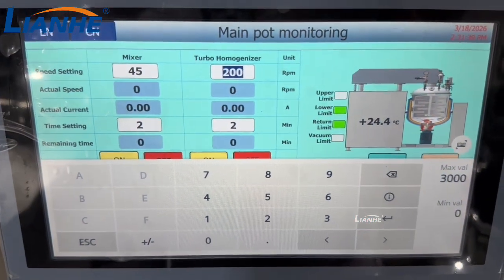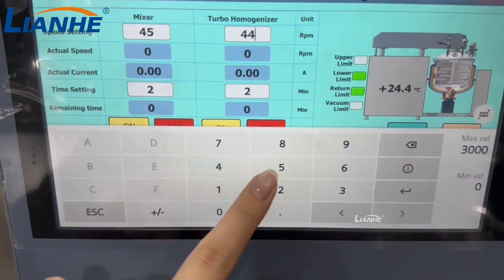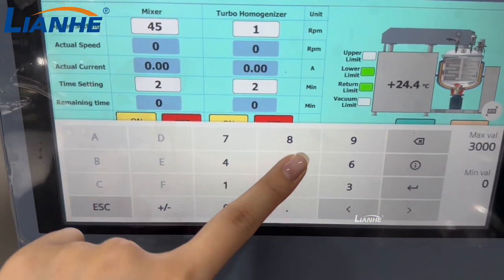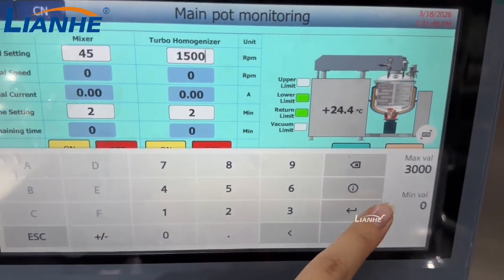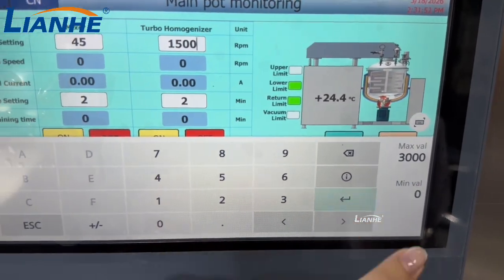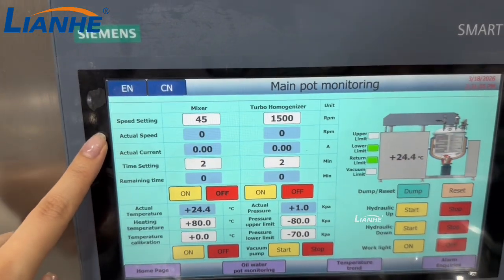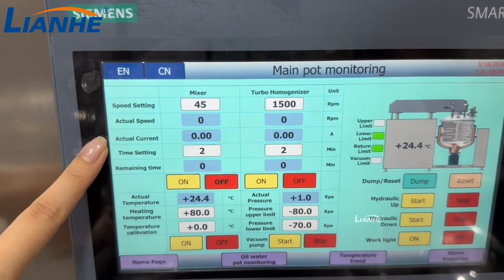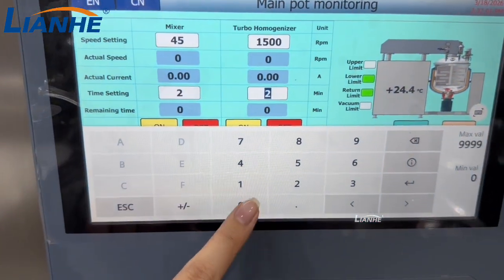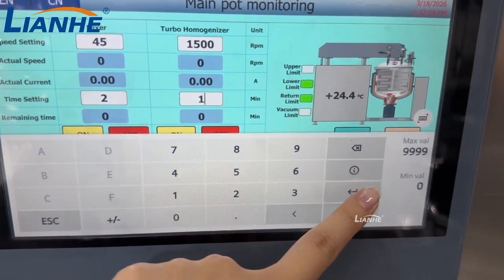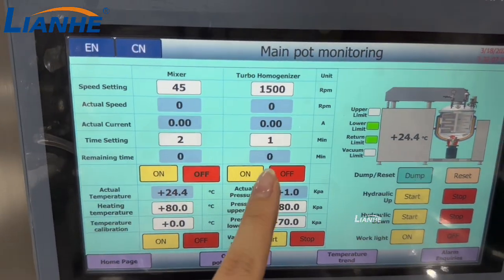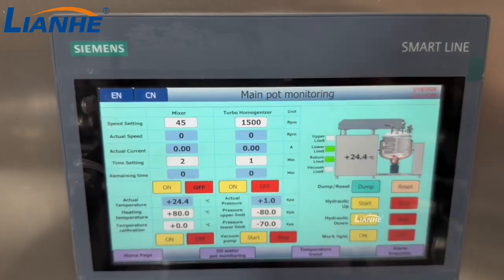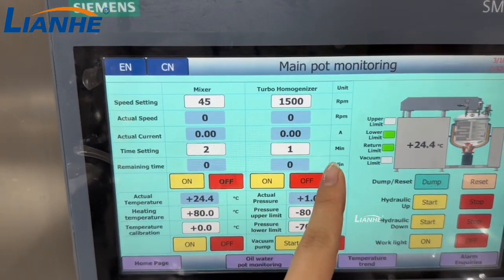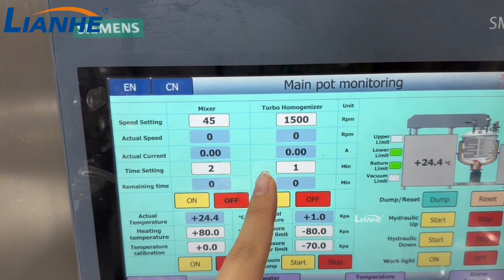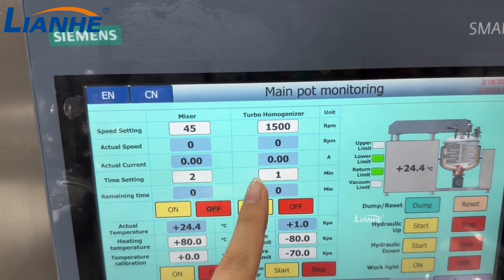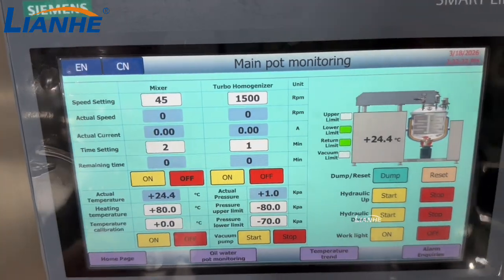You can set the speed for the homogenizer like 1,500, and the maximum speed is 3,000. You can set it here, and then the actual speed, the actual current of the homogenizer, is displayed, and then the time setting here. You can also set like 1 minute for reference, and then this is the on and off for the mixing and homogenizing function. And it's the same: when the homogenizing time arrives at 1 minute, like we just said, the homogenizing function will stop automatically.